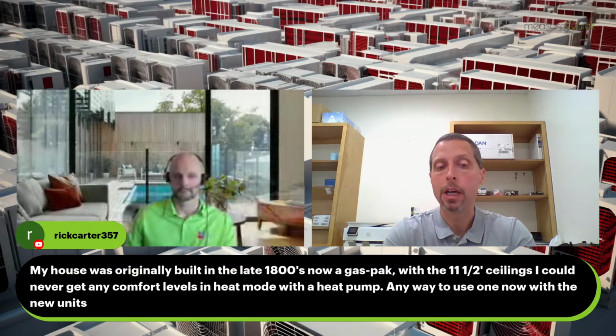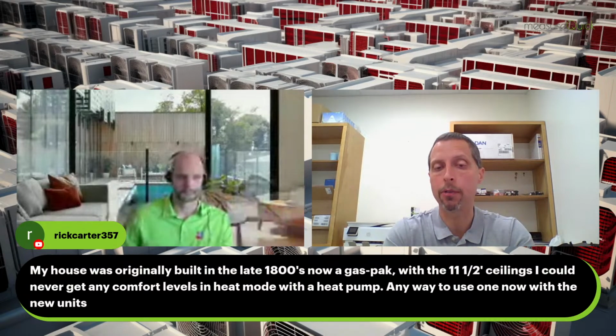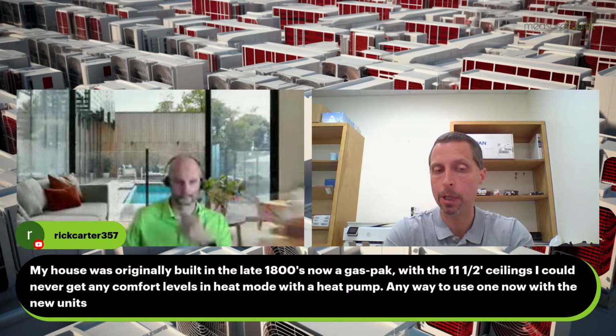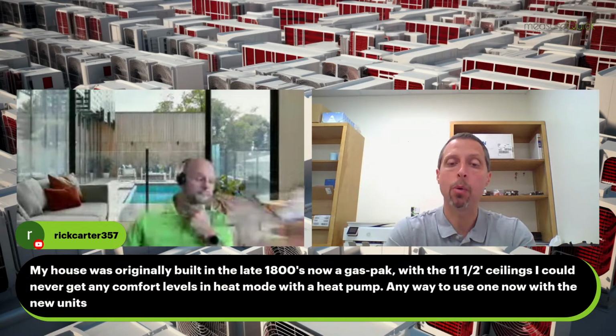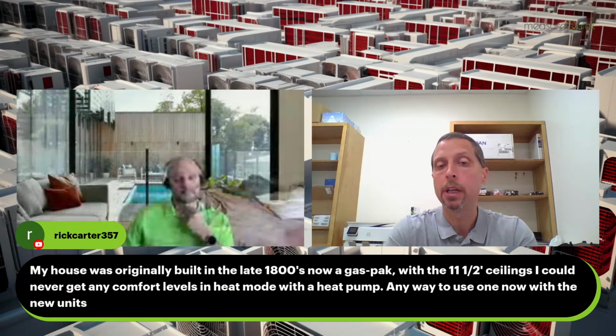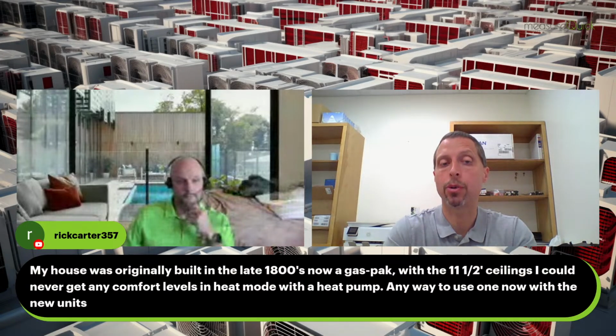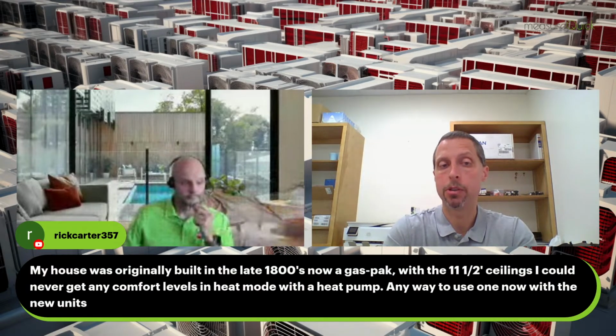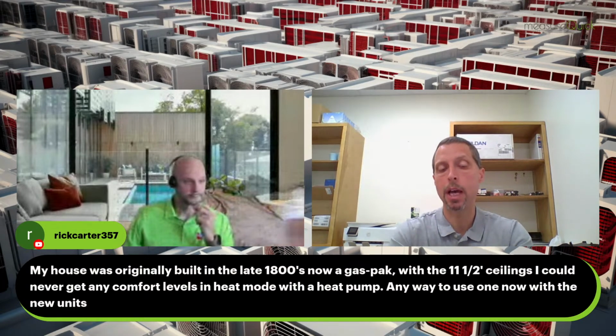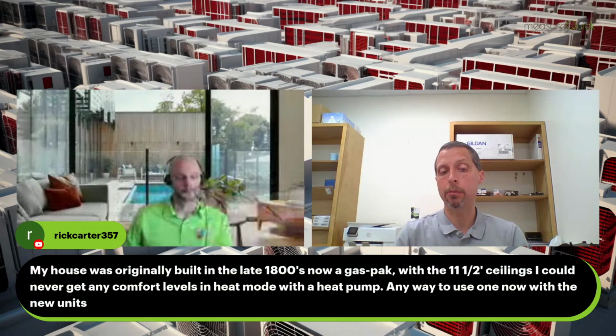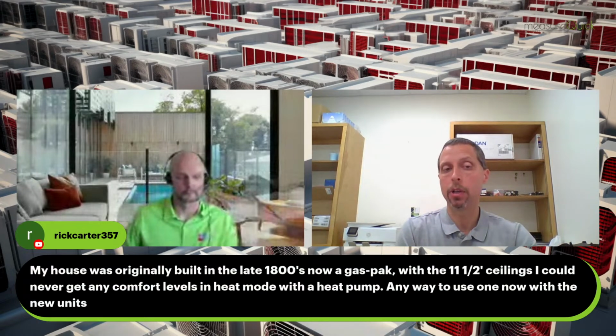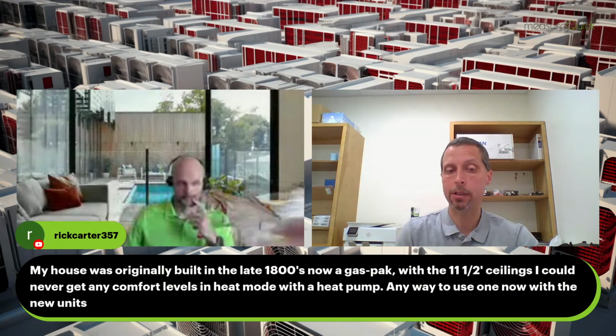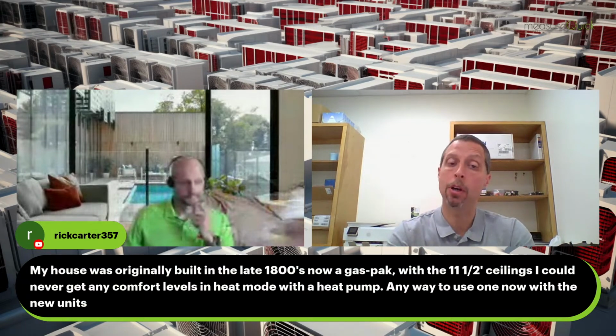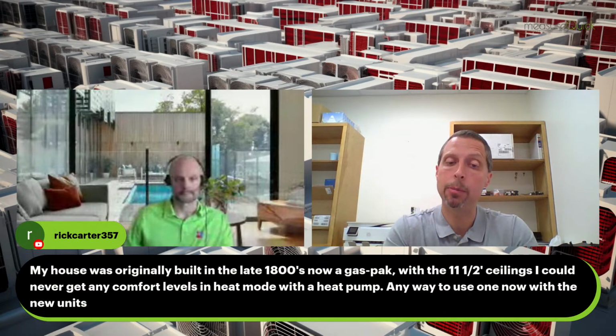That's a home with a sensible heat ratio of 0.95 or greater. So that's going to be hard to achieve for many of us. But what we're allowed to do now is basically do active dehumidification to create a dry home, to create the ability to use this dry sizing criteria. So now we can size the heat pump to meet the heating load, knowing that it'll have cooling capacity to drive down the sensible load, but knowing that we're going to struggle to dehumidify.